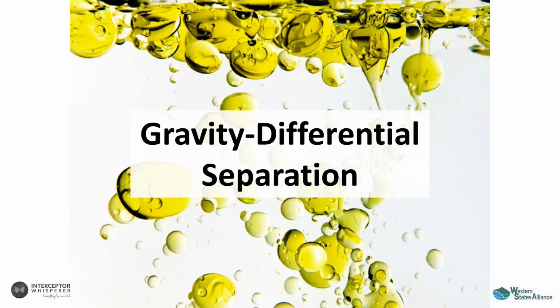Plumbing Code. One of the fundamentals that we need to understand about how all grease interceptors work, because up until now there was no distinction between types of devices, and many people today think that there is a distinction between these devices in performance. In other words, how they work. You'll hear words like, well, these devices work off of Stokes' law. I've heard people say, well, no, but these smaller devices work off of Bernoulli's principle. And the fact of the matter is that all grease interceptors work off of a simple principle called gravity differential separation. And really, I don't have time to go into all the ways in which gravity differential separation works.